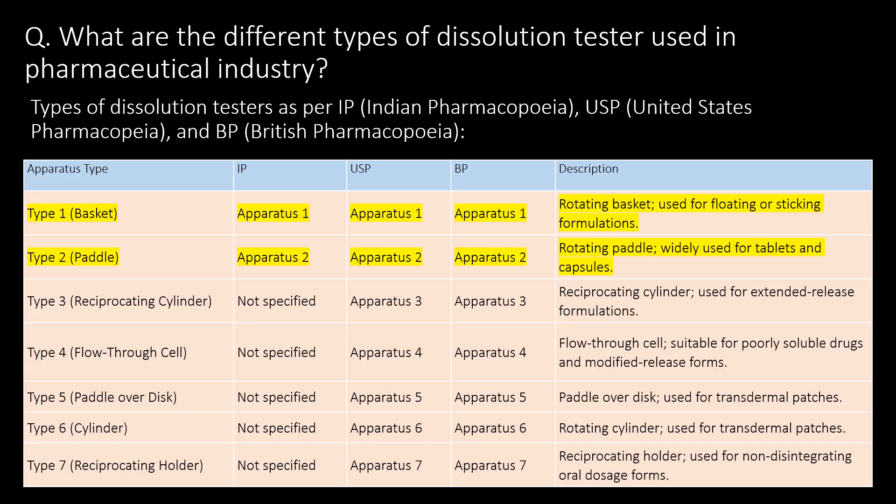A very frequently asked question: what are the different types of dissolution testers used in the pharmaceutical industry? You can refer to the bullet table for different types of dissolution testers as per Indian Pharmacopoeia, United States Pharmacopoeia, and British Pharmacopoeia. The two most commonly used are Type 1 — basket type, also known as apparatus 1 — which has a rotating basket and is commonly used for floating or sticking formulations; and Type 2 — paddle type, also known as apparatus 2 — which has a rotating paddle and is widely used for tablets and capsules.